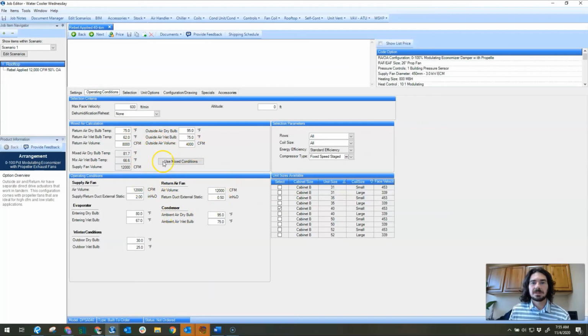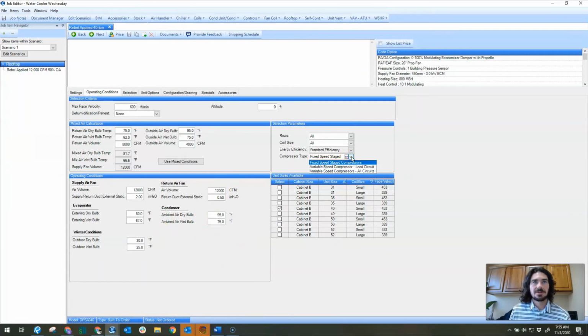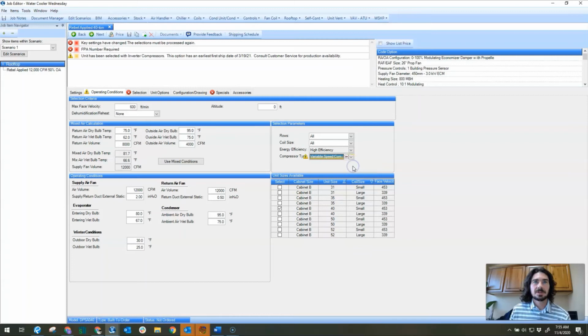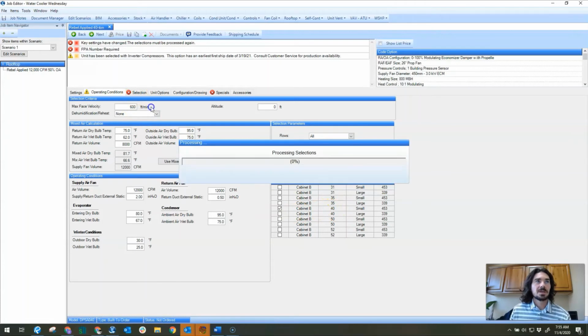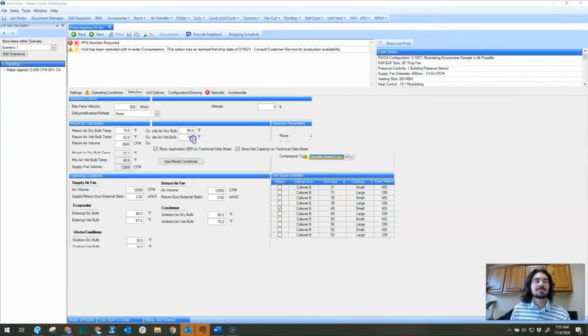You can customize your design criteria here: CFM, static pressure, entering air temperatures, all of that. You can also select between fixed speed compressor or variable speed. In this case, I'm going to do variable speed on the lead circuit, just for fun. And I've got a 40-ton target here. We're going to see how that comes out. So we're going to do a selection here.